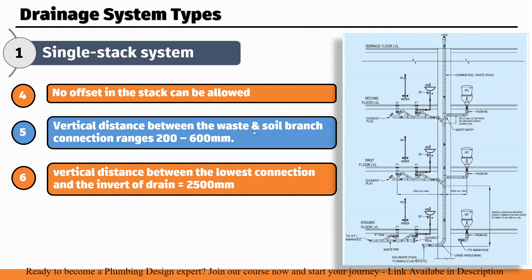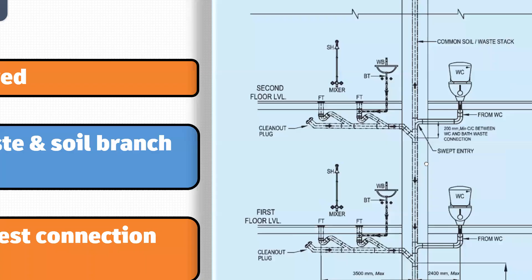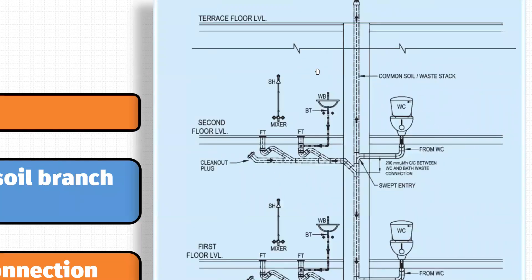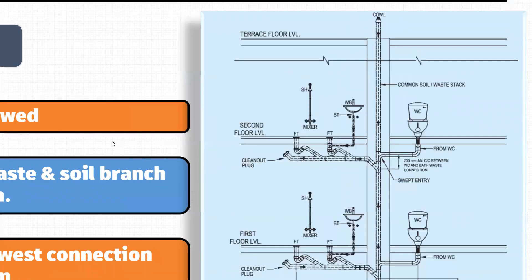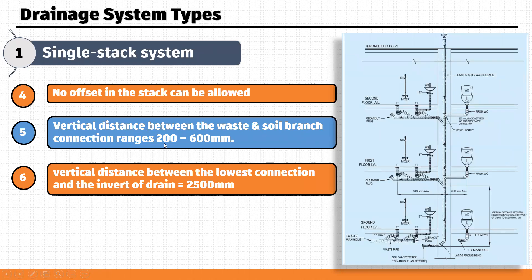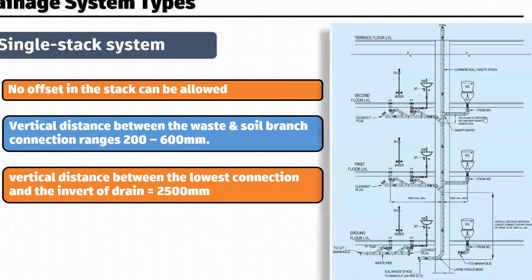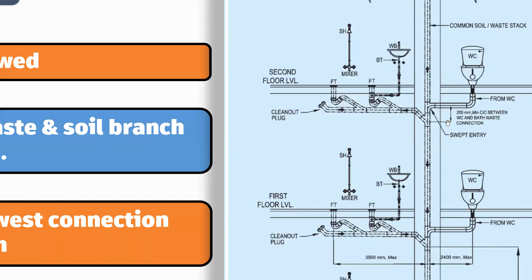The sixth point: the vertical distance between the waste branch connection and the soil branch connection to the common stack must range from a minimum of 200 mm to a maximum of 600 mm. The center-to-center distance between these two connections must be at least 200 mm and not more than 600 mm.